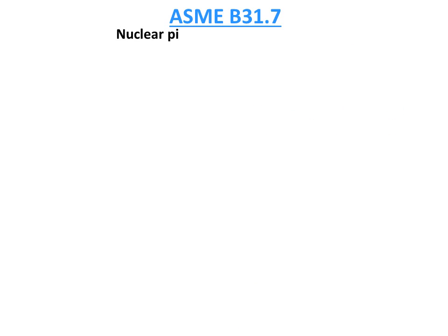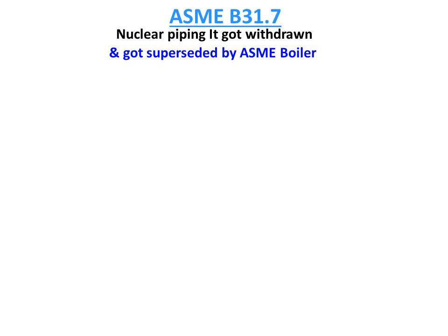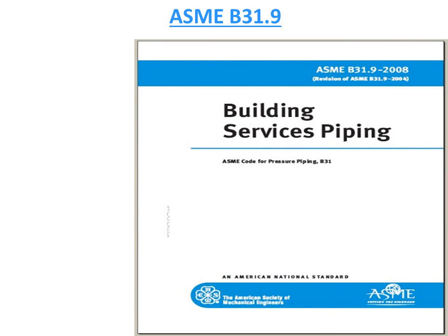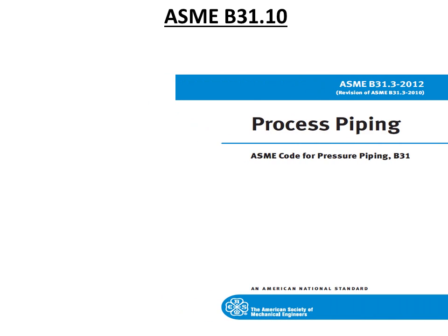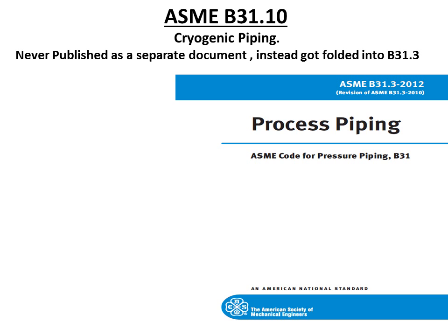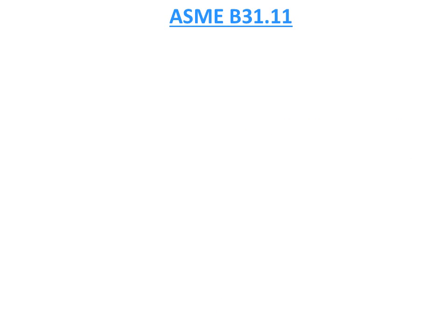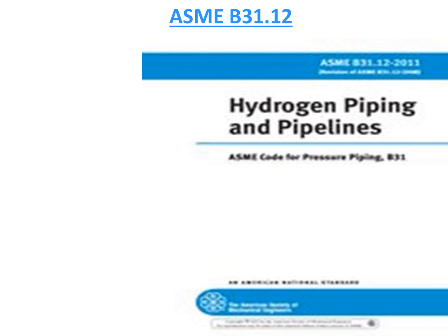B31.7 was meant for nuclear piping and that work was withdrawn. ASME B31.8 is for gas transmission and distribution piping systems. ASME B31.9 is for building services piping. ASME B31.10 was meant for cryogenic piping but was never published as a separate document and instead got pulled into B31.3 itself. ASME B31.11 is for slurry transportation piping. ASME B31.12 is for hydrogen piping and pipelines.